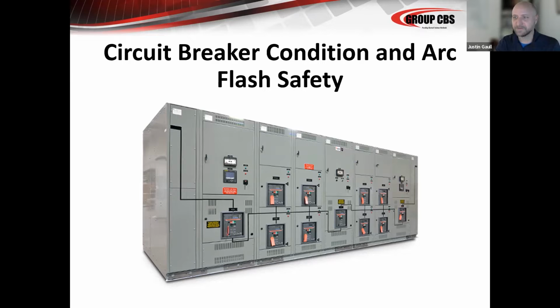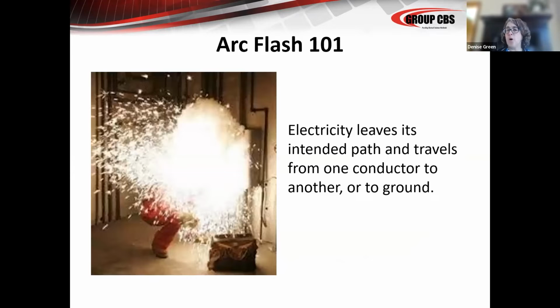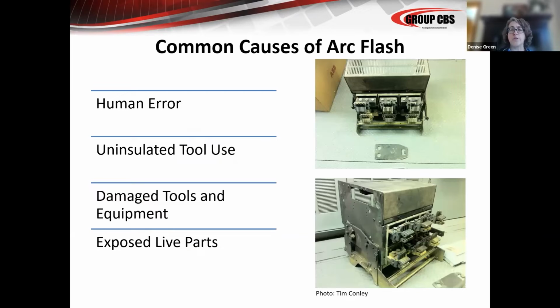So as Justin said, we're going to talk a little bit about circuit breaker condition and how it affects arc flash safety. As you all know, Arc Flash 101, electricity leaves its intended path, either goes phase to phase, phase to ground, and that's how an arc flash occurs. The implications of breaker maintenance on arc flash situations can be very severe. So that's why we're talking about this and hopefully spreading a little bit of awareness about how those components affect the people that are standing in front of the cell and dealing with the breakers.